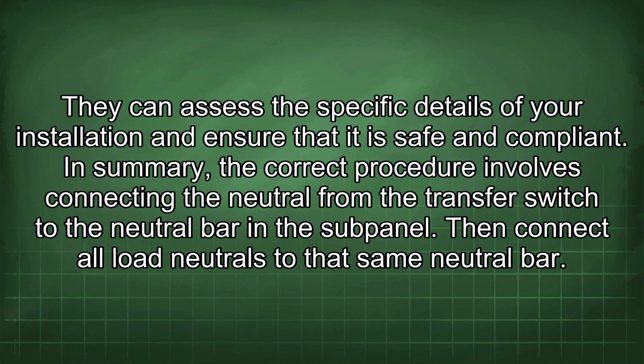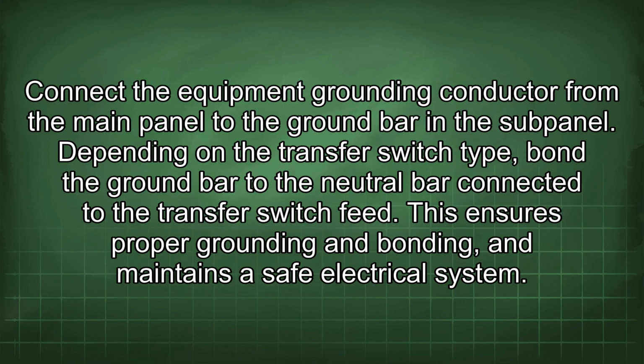In summary, the correct procedure involves connecting the neutral from the transfer switch to the neutral bar in the subpanel. Then connect all load neutrals to that same neutral bar. Connect the equipment grounding conductor from the main panel to the ground bar in the subpanel. Depending on the transfer switch type, bond the ground bar to the neutral bar connected to the transfer switch feed. This ensures proper grounding and bonding and maintains a safe electrical system.